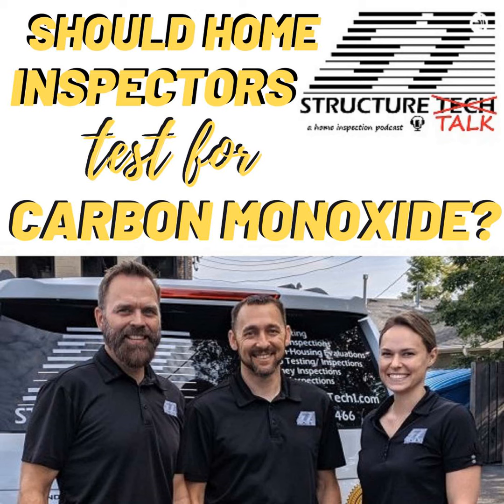They don't spell it out quite that way. I think maybe the new version of the code does, but the way it was always written in the code was that it can't be more than 0.04, like 4/100ths of a percent, which equals 400 parts per million. They didn't actually say 400 parts per million in the code. It was 0.04%. It can't exceed that. And if it does, it's bad news.